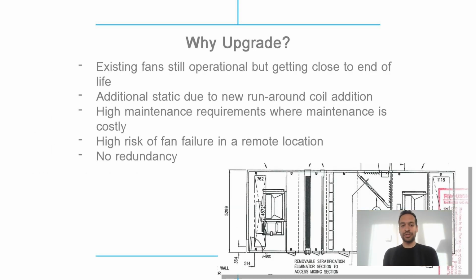And their main reason to upgrade was, first, they did not want to go through a catastrophic failure of the fans, because it would have been a disaster in the cold in winter if one of the fans failed. It's a remote location, so it would have taken a long time to just transfer and ship these fans to the location. And winters are very difficult for maintenance, for replacing the fans.